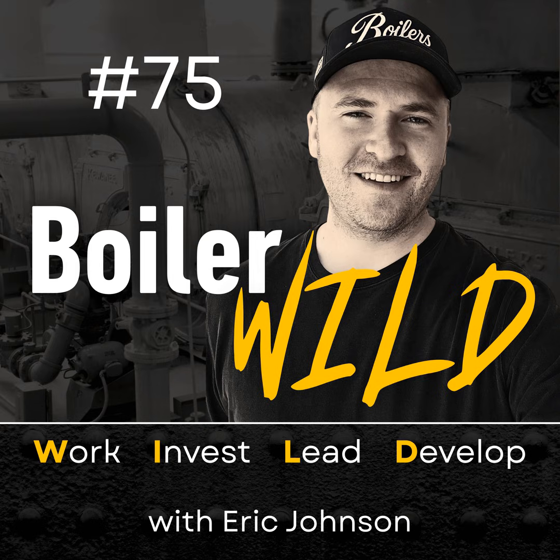It's the last thing that is commissioned, in my experience commissioning boiler rooms. Most of the time you have some general contractor telling you that you need steam, and then you're kicking back to him. He's like, well, you want steam? I don't even have the water softener piped, so we need to get that going first. So once we bring on the system from softener to tank to chemical dosage, and make sure water levels are controlled in the tank, then we can get steam. Usually the last thing, even after the controls, is the monitoring, because they want to at least live fire the boiler and run steam through a plant, and then they'll worry about monitoring after the fact.